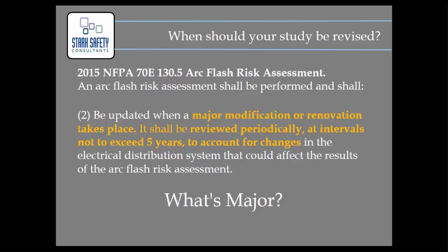We don't want to lose sight of fuse changes, breaker setting changes, transformer changes, or reconnecting devices to a different connective device in the system. Those could be major and could affect big parts of the system. The worst case is just saying you don't have to do anything for 5 years even though you know it has affected your system. At the end of the day we're looking at safety, so we should look at those things and see what they actually do to the system.